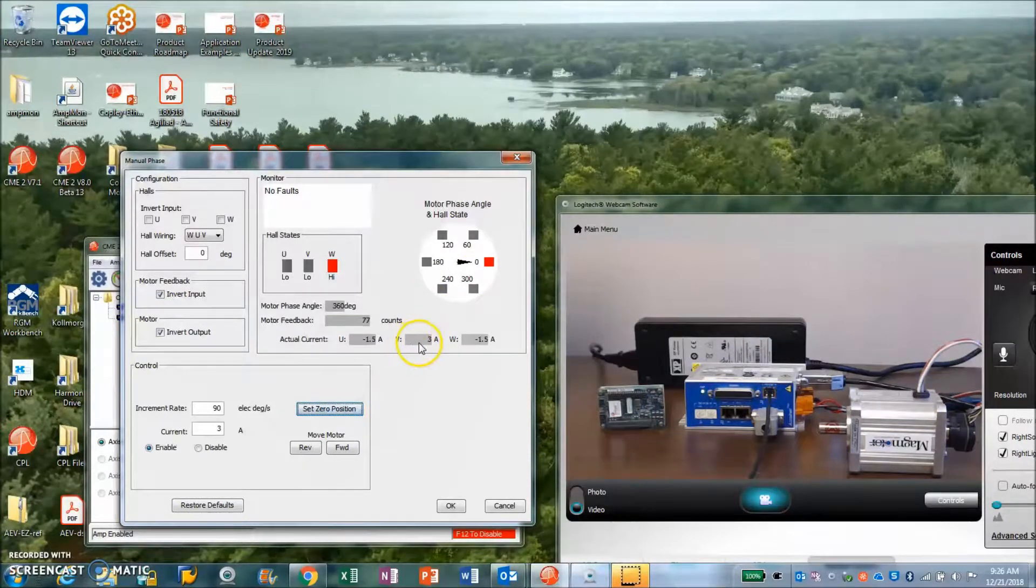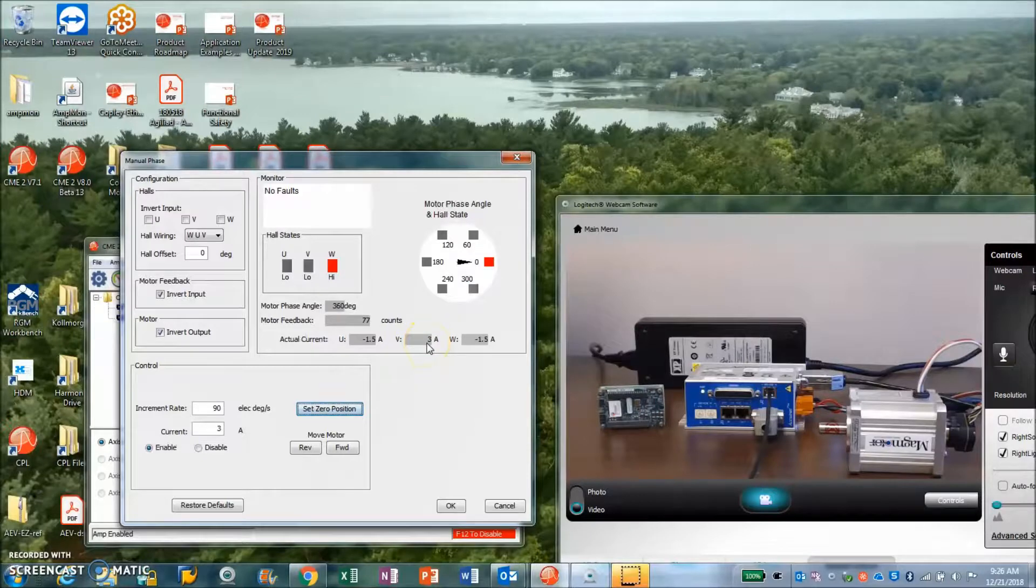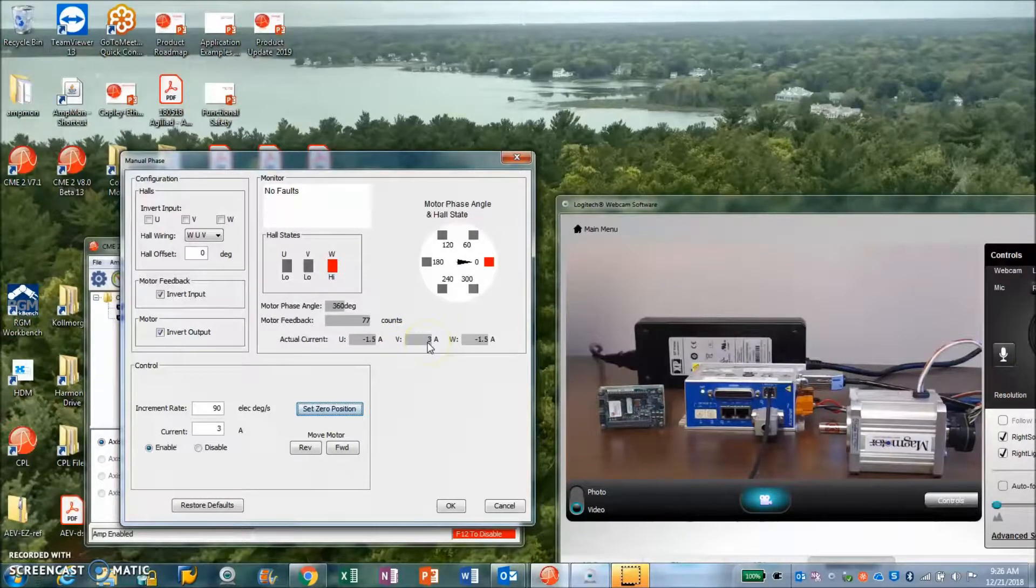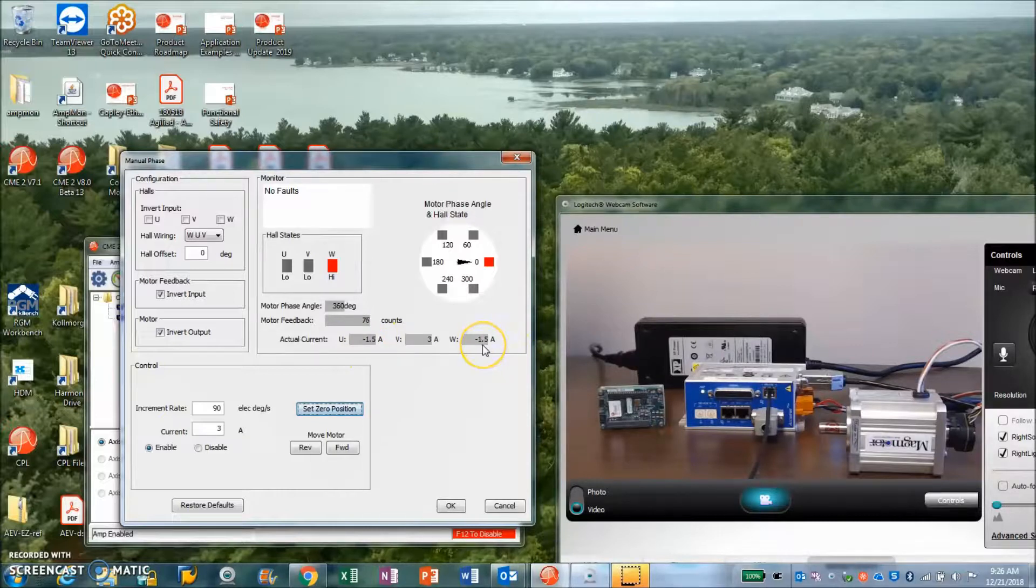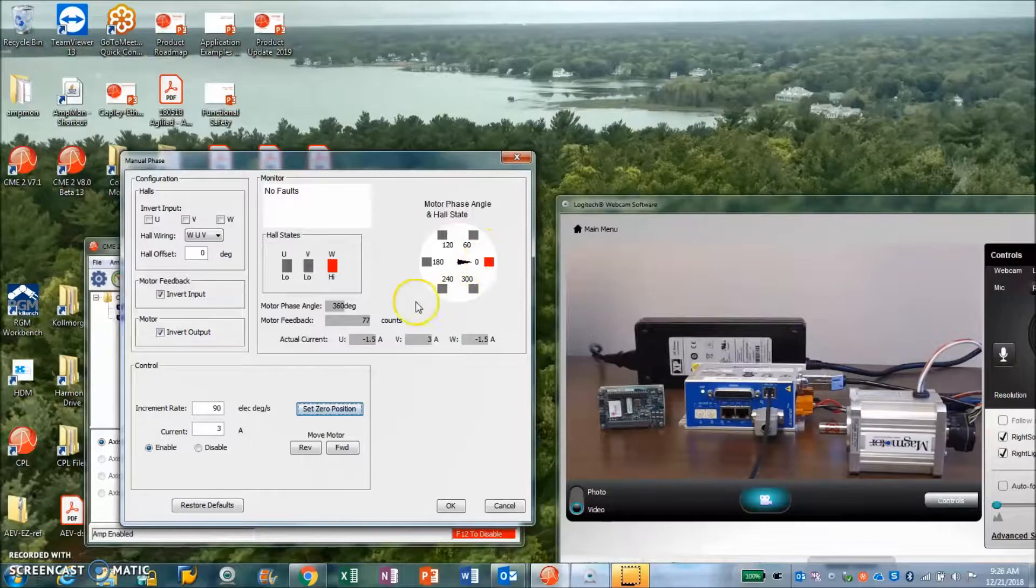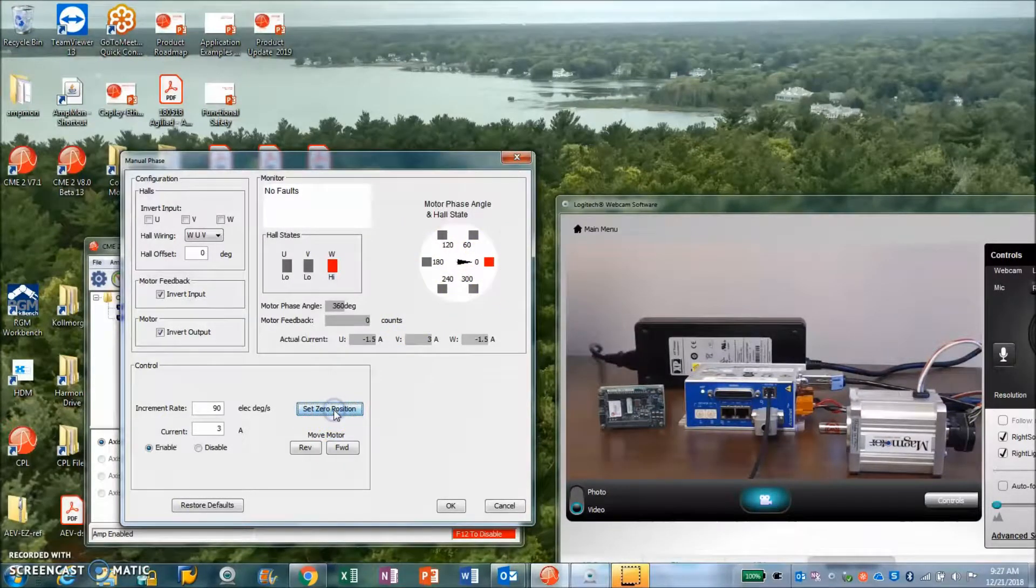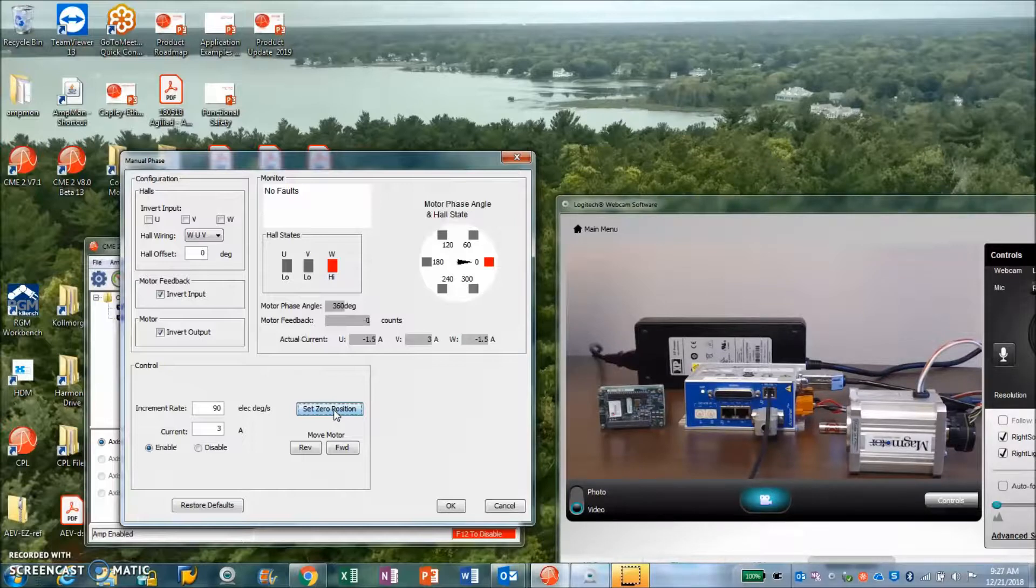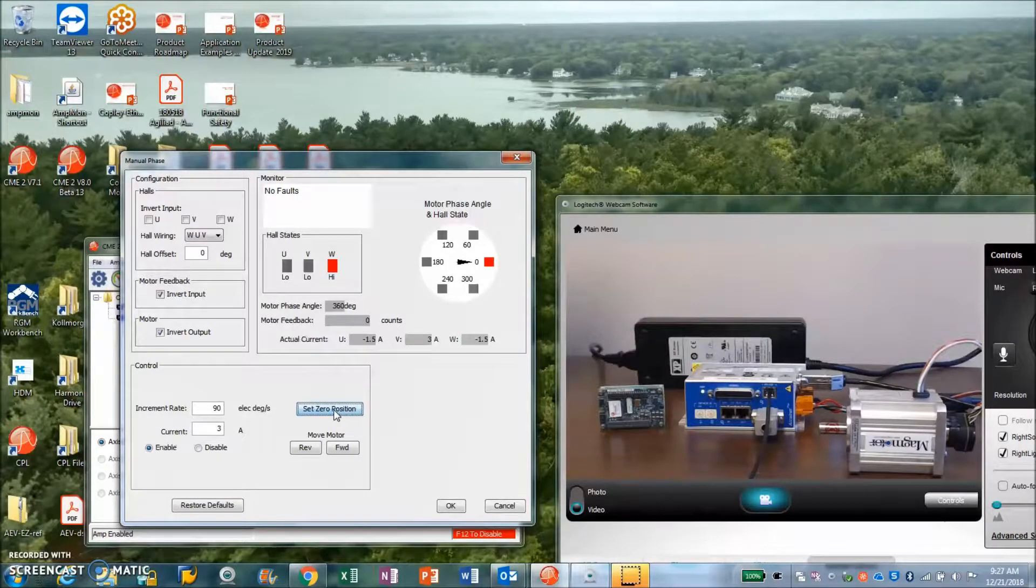You can see in this test setup, this is like a motor manufacturer. They'll pump three amps into U, split it down V and W, thereby locking the shaft, and then rotate the hall to the right code, and then we have a perfectly aligned for commutation feedback device, even with an index marker according to the reference indicator.